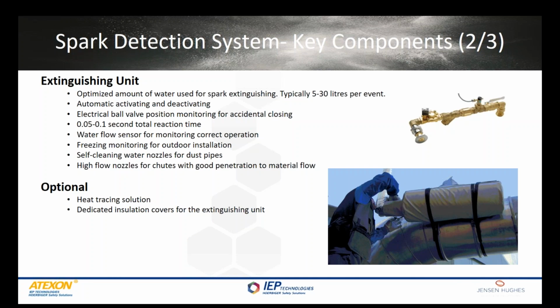The second key component is the spark extinguishing unit. This rapid extinguisher can produce full coverage water spray in the protection area within 50 to 100 milliseconds, depending on the application. Typical amount of extinguishing water is something like 5 liters for dust extraction pipes and 20 to 30 liters for conveyor chutes. Electrical ball valve monitoring systems are available so that accidental valve closing can be monitored. A water flow sensor is very important for each protection area to localize possible water leaking or lack of extinguishing water during an alarm.